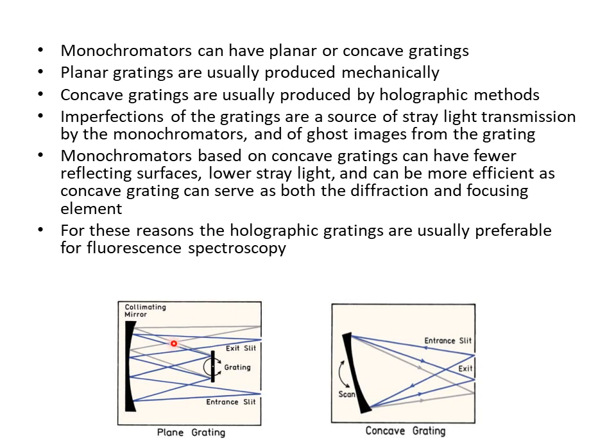As shown in the figure, here is the planar grating and here is the concave grating. Planar gratings are usually produced mechanically while concave gratings are produced holographically. If these gratings are produced inaccurately — if there are imperfections — these will be a source of stray light transmission by monochromators. The manufacturing of the grating is a very important step, as any problem may cause stray light transmission and ghost images.